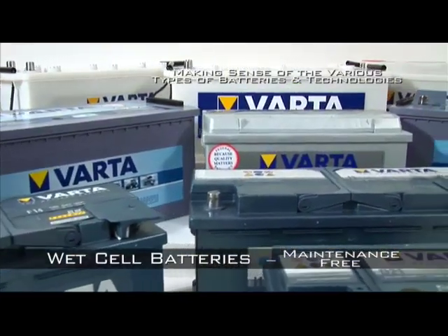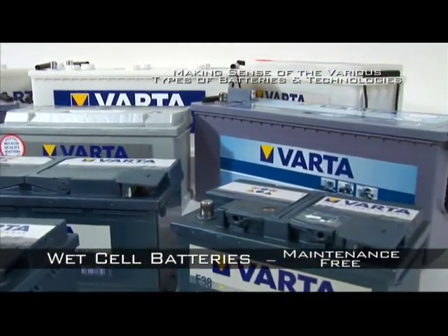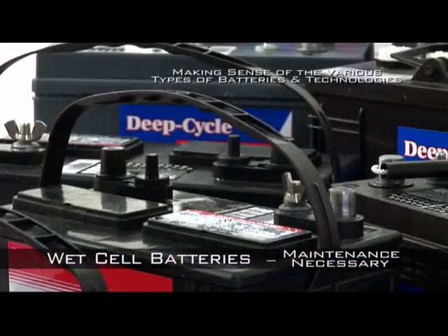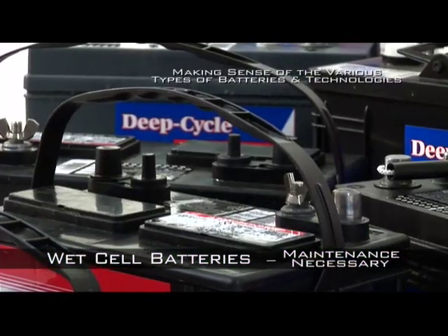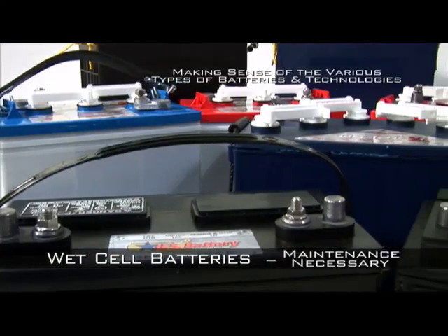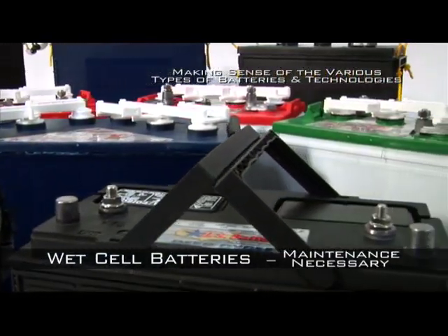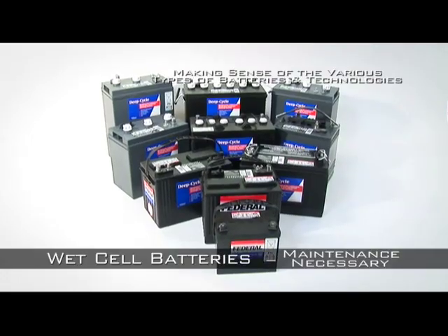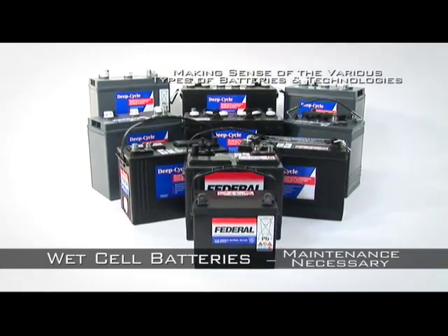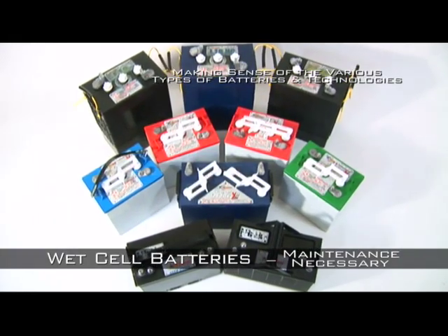Calcium technology successfully reduces gassing so that the battery becomes largely maintenance-free. Yet it also has the effect of increasing plate degradation in heavy cyclic use. Therefore, it is not a common feature of batteries designed to withstand the damaging effects of continual deep discharge and recharge. This trade-off results in a shortened service life, and therefore with Wet Cell deep cycle batteries, it is necessary to use traditional top-up batteries with antimony mixture, heavy thick plates, and fibreglass reinforcement.